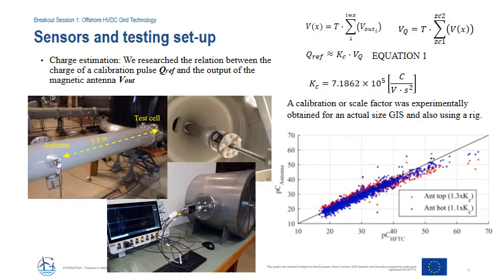Both an actual size GIS and a calibration rig were used to research the limits of the charge estimation. The underlying reasoning of the experiments was to inject a calibration pulse from which a reference charge is calculated, and to process mathematically the output signal of the antenna to ultimately seek the relationship in equation 1. The results showed that the scatter is low, therefore a calibration factor is feasible.